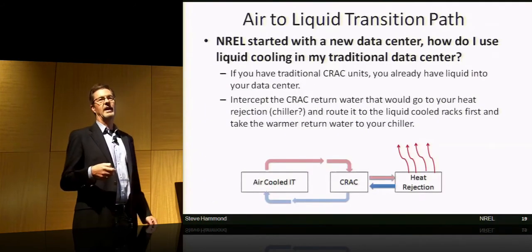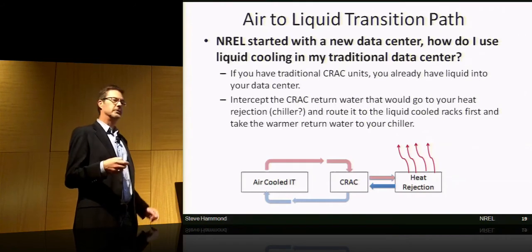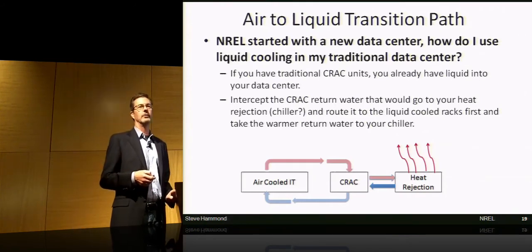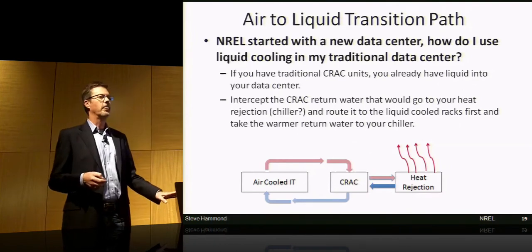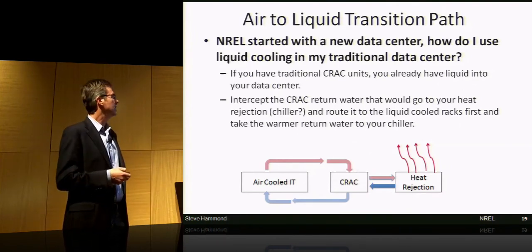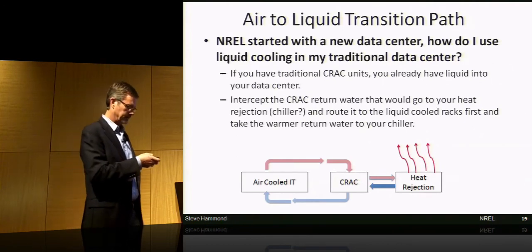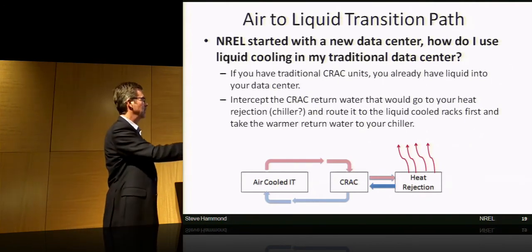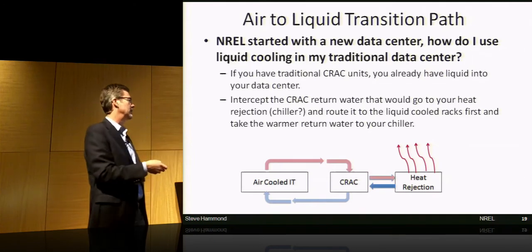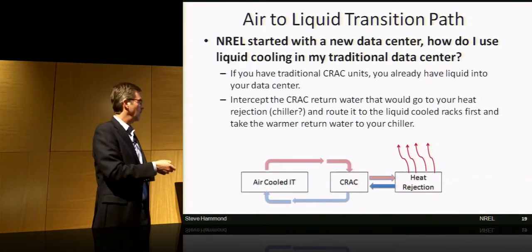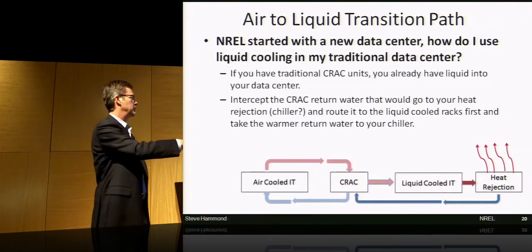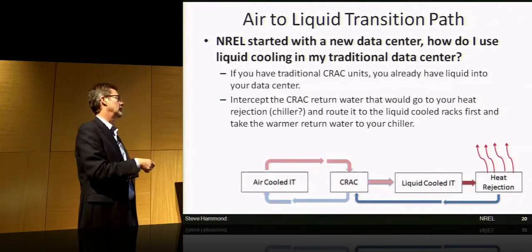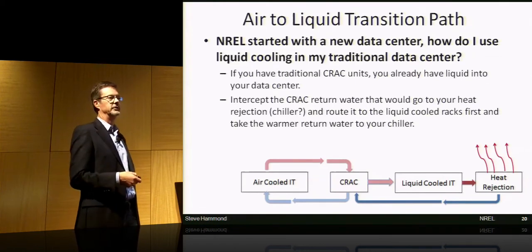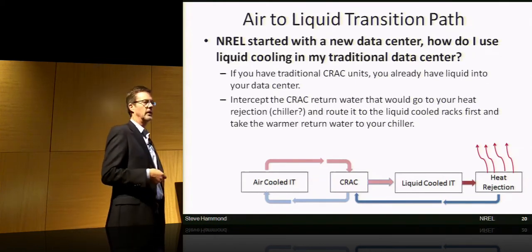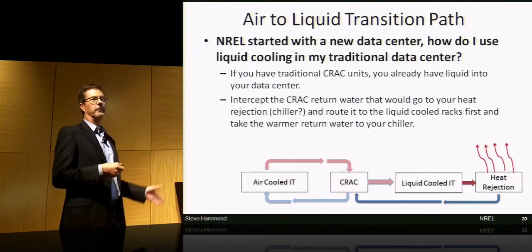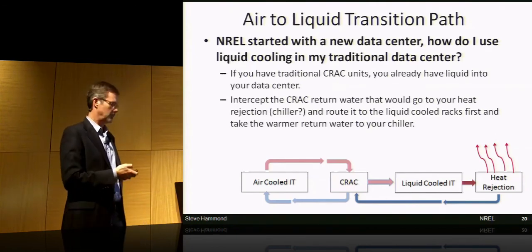One of the most common questions I ask is, I've got a legacy air-cooled data center, and you had the benefit of building a whole new data center. What could I do to start a transition? A typical data center does have liquid in it. There's liquid that goes to your CRAC unit, and that just generates cold air. So what you could do is put in your liquid-cooled system and grab the CRAC return water, feed that to your liquid-cooled system, and then return hotter water to your heat rejection. So there are fairly straightforward ways to intercept and do that.